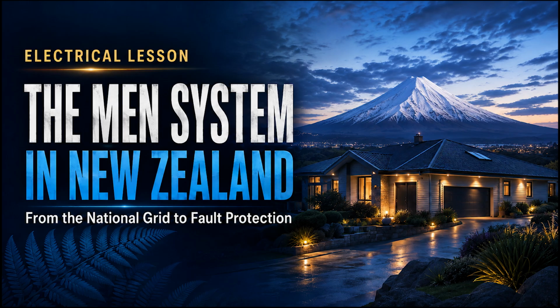Question 7. What is the role of the earth electrode? It connects the earthing system to the general mass of Earth, establishes an Earth reference, and contributes a parallel path. It is not normally the main metallic fault current return path. Question 8. What makes automatic disconnection work? A reliable low-impedance fault loop together with a protective device that disconnects within the required time.